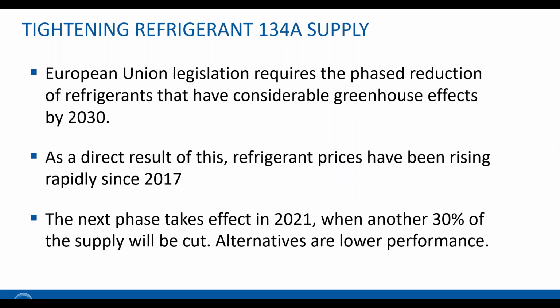And then there is, of course, the question of sustainability. One factor to consider here is that the commonly used refrigerant for compressors, refrigerant R134a, is actually being phased down already aggressively in the European Union, and we also see some of the markets, including the US, following suit in a not too distant future.